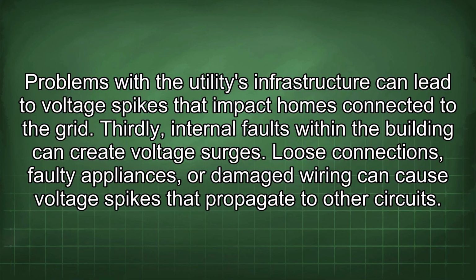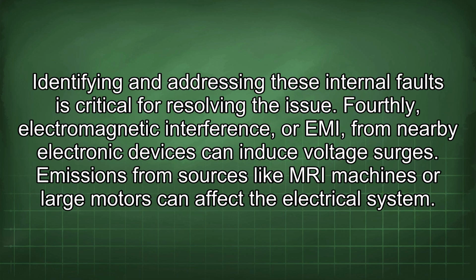Thirdly, internal faults within the building can create voltage surges. Loose connections, faulty appliances, or damaged wiring can cause voltage spikes that propagate to other circuits. Identifying and addressing these internal faults is critical for resolving the issue.